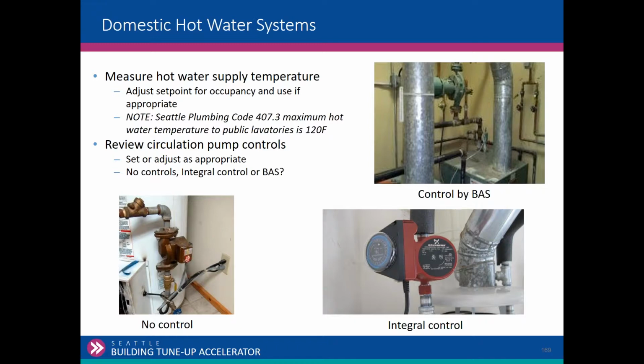A lot of the circulation pumps now have integral control, so they've got a timer built right into the circulation pump. Is the timer set at the right time, right day of the week? Is it even set at all? If you run across a mechanical time clock, are the settings correct? Or are all the pegs missing and laying in the bottom of the box? I'm sure a lot of you have seen that before. So, pretty straightforward: temperature and circulation control on the domestic hot water side.